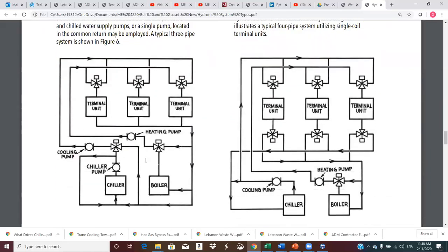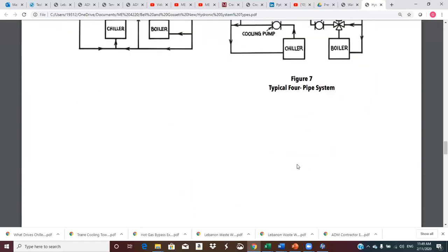In the 4-pipe systems, this simply means that each air handler or terminal unit has the ability to receive either hot water or chill water at the discretion of its controls. So we're showing a 3-way valve here. I've got my boiler, my hot water coming up here. This is confusing, as I'll get out. Okay, so we can feed hot water into the terminal unit, or we can feed chill water into the terminal unit, and they should return separately either to the chiller or boiler. That's a little confusing, but that's what it's getting at.